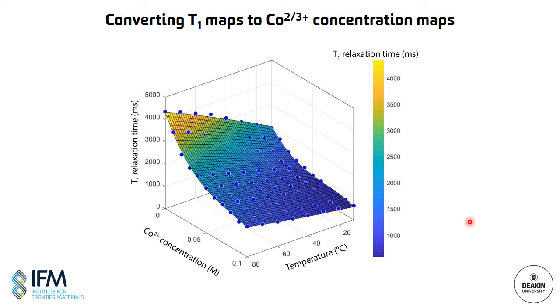So the next thing we want to do is connect the electrodes to the external load and try to observe the resulting redox reactions in the form of concentration maps. The problem here is that the measured T1 value for each pixel will depend on both the temperature at that point and the relative concentration of the redox species. Fortunately, we already have the temperature maps from the unconnected cells, and we assume that the spatial variation in temperature is unaffected by the redox reactions once we connect the electrodes.